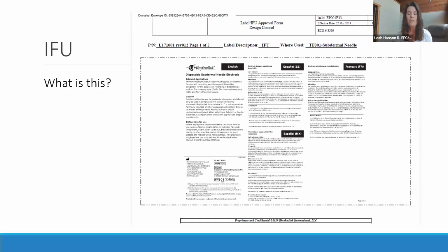For instance, you've got a suite that's got an integrated MR system. So for MRI, you've got to know if the devices that you're using on that patient are approved and cleared for MR. And it is going to say it clear as day in that IFU. If it doesn't say it, there's an assumption it's not. And if you're not sure, call the vendor. But again, if it's not in there, it's not. So I would really familiarize yourself with those documents. You don't have to read it every single time, but knowing where it is, knowing where to find it, and knowing who to ask if you can't find it really takes the responsibility of those details from you as the responsible person in that moment to sharing it with that manufacturer and getting the right answer where it needs to be.